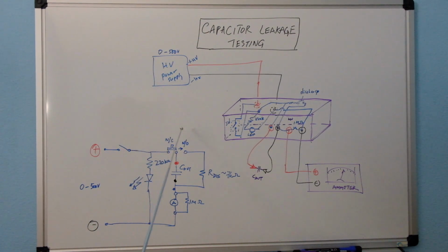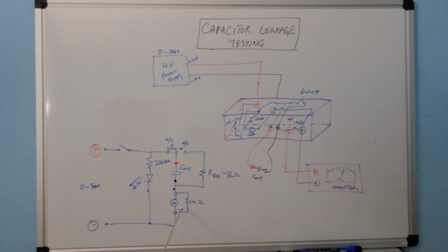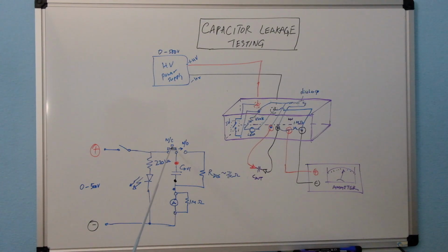And then the main capacitor charging path is through this switch over here, a normally closed switch, and the capacitor leakage is measured on the return side through this ammeter over here. If you want to discharge the cap, you can move the switch to the other side, and it will disconnect the supply from the cap itself, but it will connect this resistor across the cap, which will then discharge it fairly rapidly, depending on how long you want to wait.